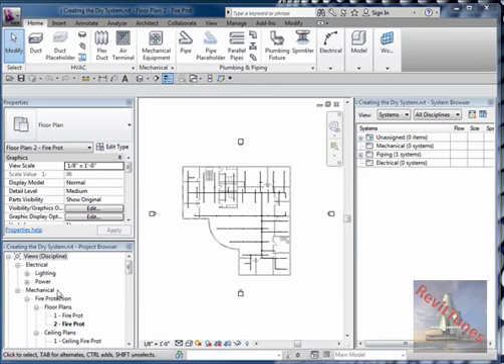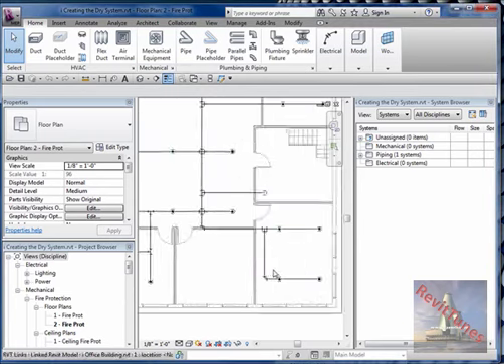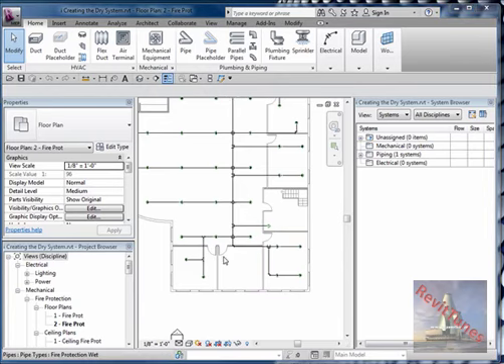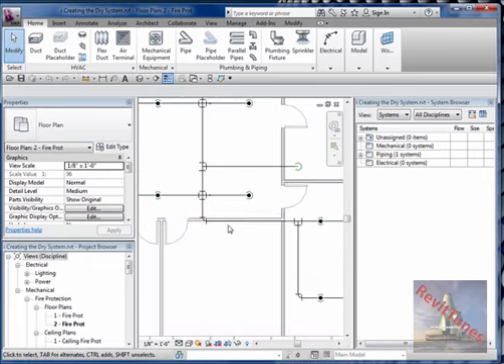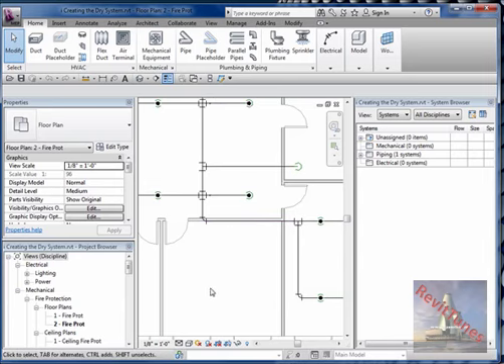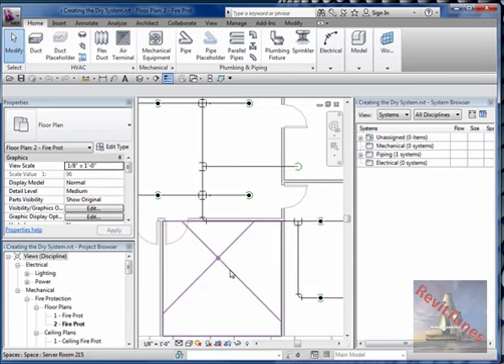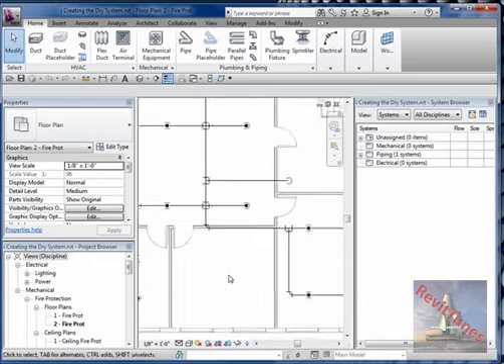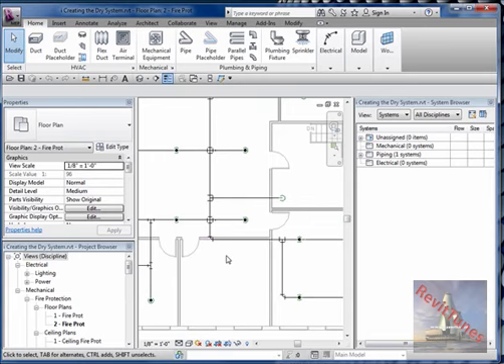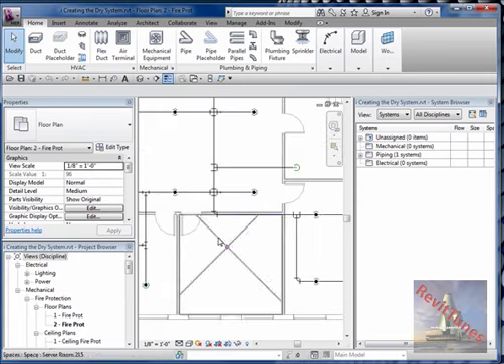RevitTunes.com. Let's go back to dry system. Let's explain why we use a dry system. Wet system, always will have water. Dry system will have a valve and separate this. This portion will be always dry until this valve opens and water comes and sprinkles the room in case of fire. But it keeps all the time empty pipes unless there is a fire. The reason is because it could be a computer room or any equipment that is in danger if there is water overhead. That's why they call it dry system that is controllable by a valve.